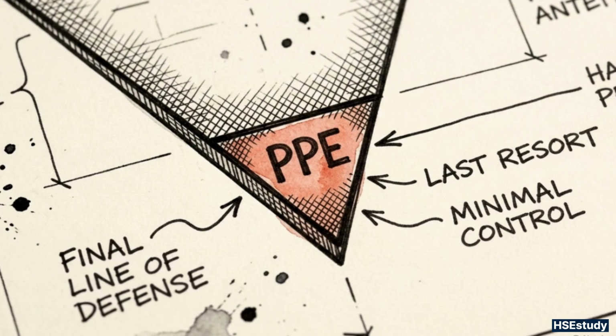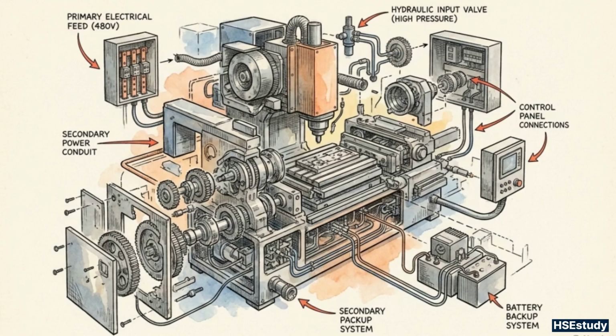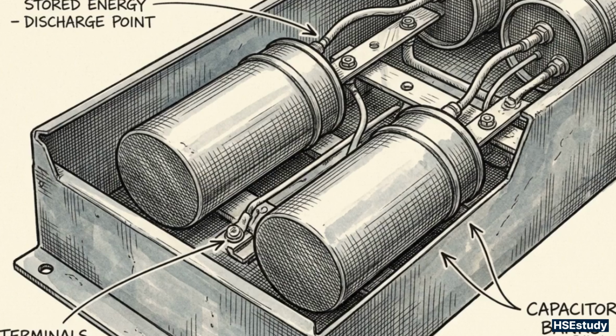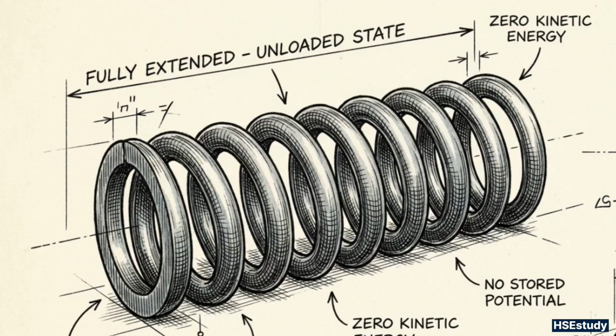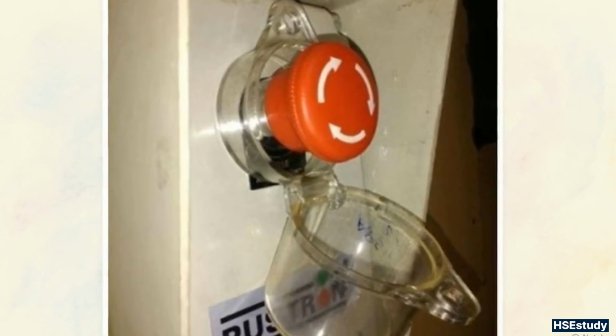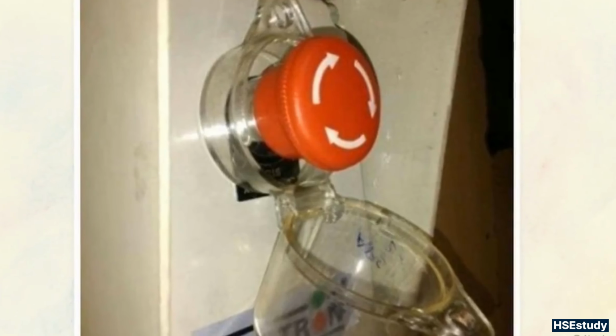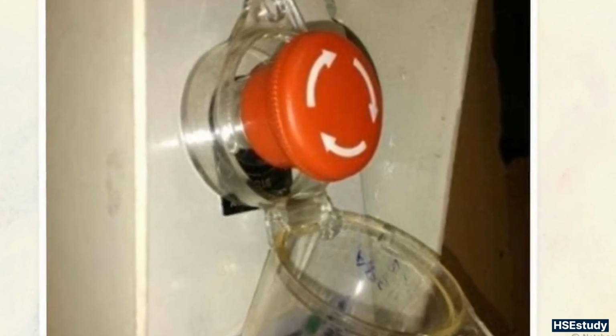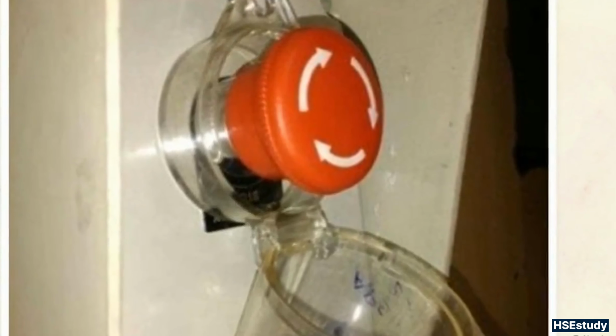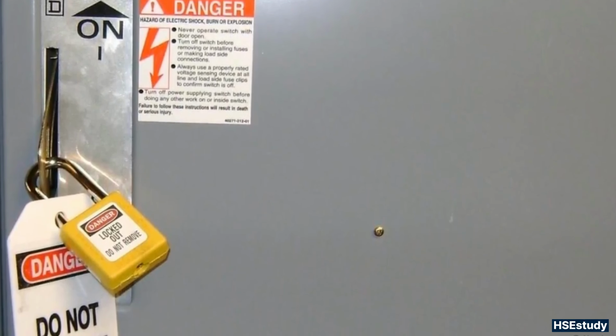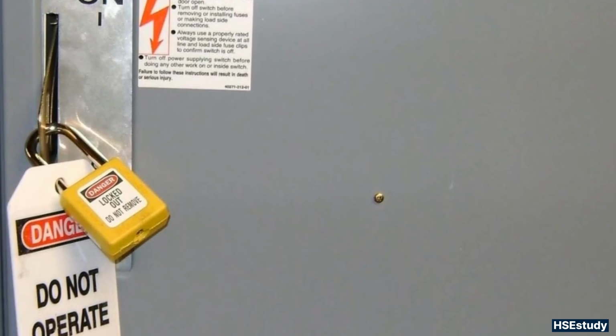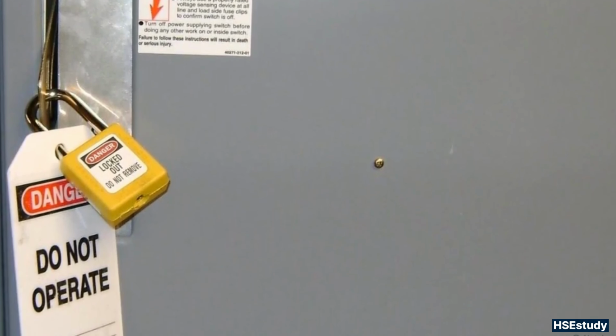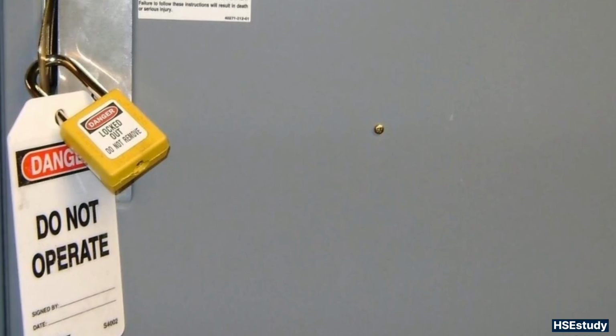The first step is mapping every energy source feeding the machine. This explicitly includes discharging stored energy in capacitors, unloading springs, and bleeding off pneumatic pressure. Pushing an emergency stop button or relying on an interlock is an improper lockout method. Control devices do not physically isolate the circuit. Approved disconnecting devices physically sever the energy path. They must be secured with an individual padlock that guarantees the switch remains open.